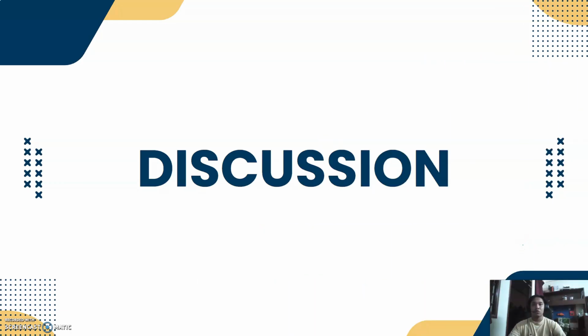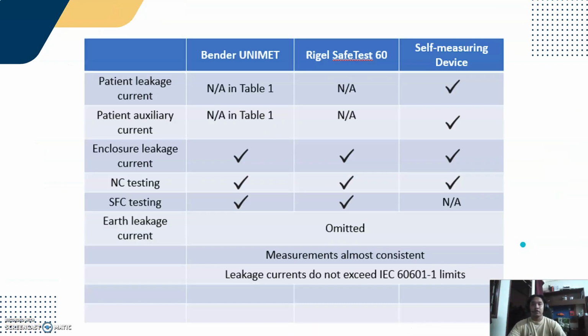Hi, I'm Ku, and now we will proceed to the discussion. There are no values for patient leakage current and patient auxiliary leakage current in table 1 for Bender and also in Rigel, as applied parts are not connected. Earth leakage currents are measured but omitted, as the tonometer is a class 2 equipment which does not have protective earth. Testing in single fault condition is not carried out using the self-measuring device as it is not fused, which may cause electric shock. Measurements are almost consistent across all test sequences and conditions and do not exceed IEC 60601 limits.